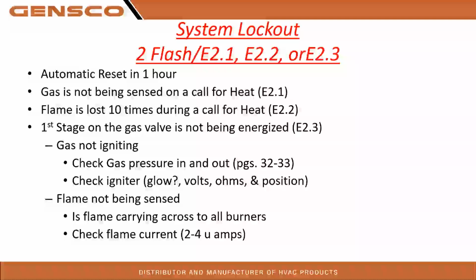So obviously flame's not being sensed. So are we carrying it across all the burners? Are we getting a full light of that burner face? We can check that with flame current checks. 2 to 4 is normal. On the S series furnace, we make it pretty easy. We have pots there that you can put your meter on and actually check directly. On the older 40-inch furnaces, it was a little different. You'd have to span a meter in there, and we'll show some pictures of how to do that. But we're looking to see what the gas pressure is, really.